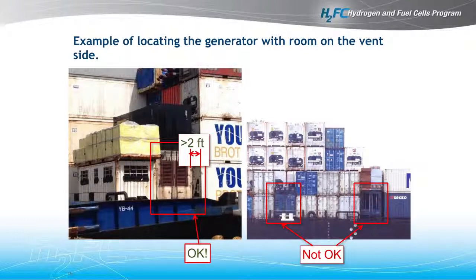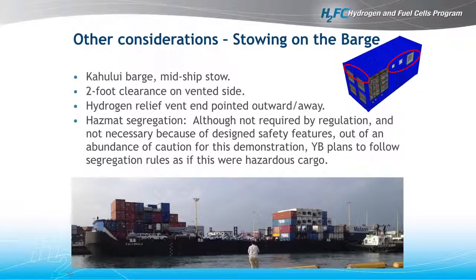So this is a demonstration of the clearance here of the 2 feet. Don't want to be smooshing it together. Now, it's not a dangerous situation. It's just that the fuel cell wouldn't be able to function properly and it would likely shut down, but it wouldn't be a hazard per se. So the 2-foot clearance on either side, and the hydrogen relief vent pointed outward and away.